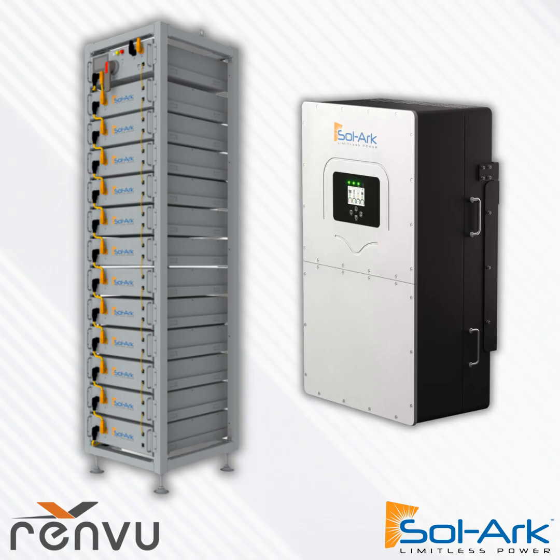Now, reducing your electric bill doesn't necessarily always have to be a very large project. So the next bit of our conversation is what time of use metering, peak shaving and demand response really look like. A lot of times you can tell if you have a good project just by looking at one paper copy of a commercial electric bill, and you can see if there's a demand charge. If the bill is mostly demand charges, then you have a good commercial project. If it's mostly energy charges, then it's probably more solar and less batteries. But just looking at the ratio between the demand charge and the energy charge can be revealing.